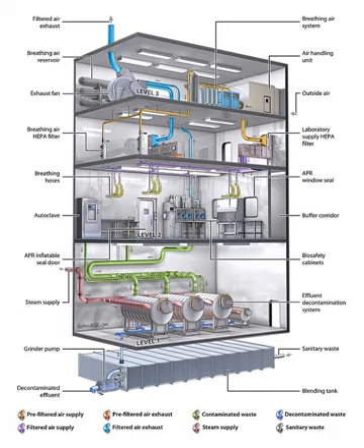Entry into the BSL-4 laboratory is restricted to trained and authorized individuals, and all persons entering and exiting the laboratory must be recorded. As with BSL-3 laboratories, BSL-4 laboratories must be separated from areas that receive unrestricted traffic. Additionally airflow is tightly controlled to ensure that air always flows from clean areas of the lab to areas where work with infectious agents is being performed. The entrance to the BSL-4 lab must also employ airlocks to minimize the possibility that aerosols from the lab could be removed. All laboratory waste, including filtered air, water, and trash must also be decontaminated before it can leave the facility.